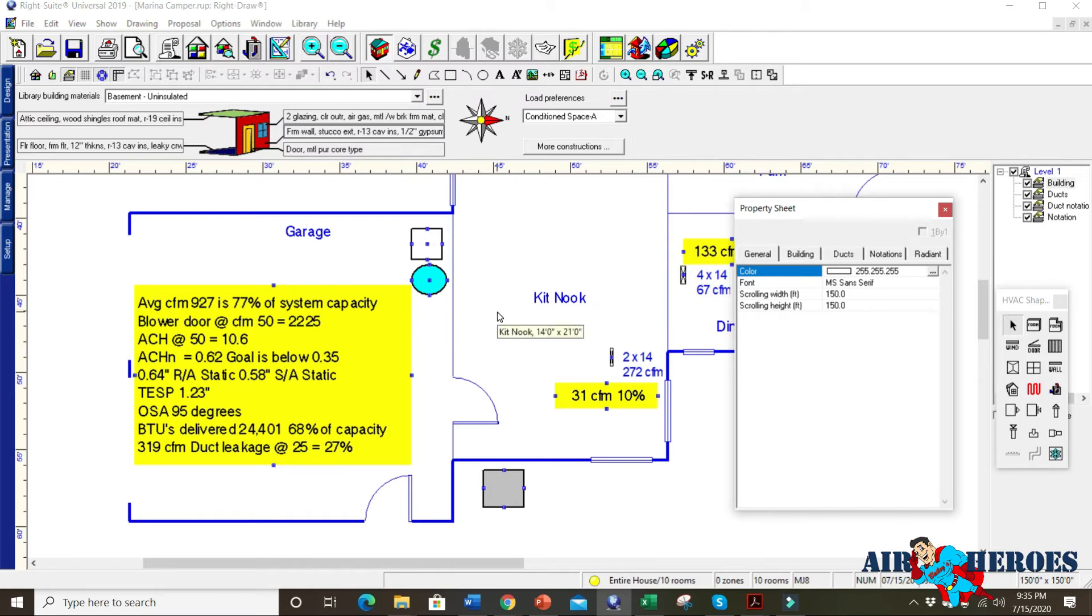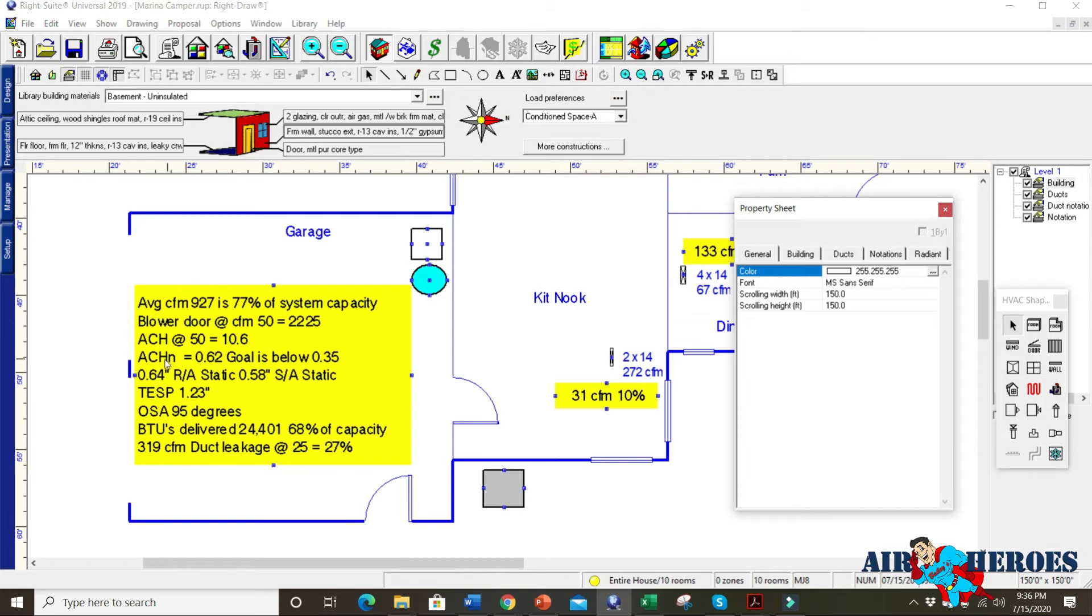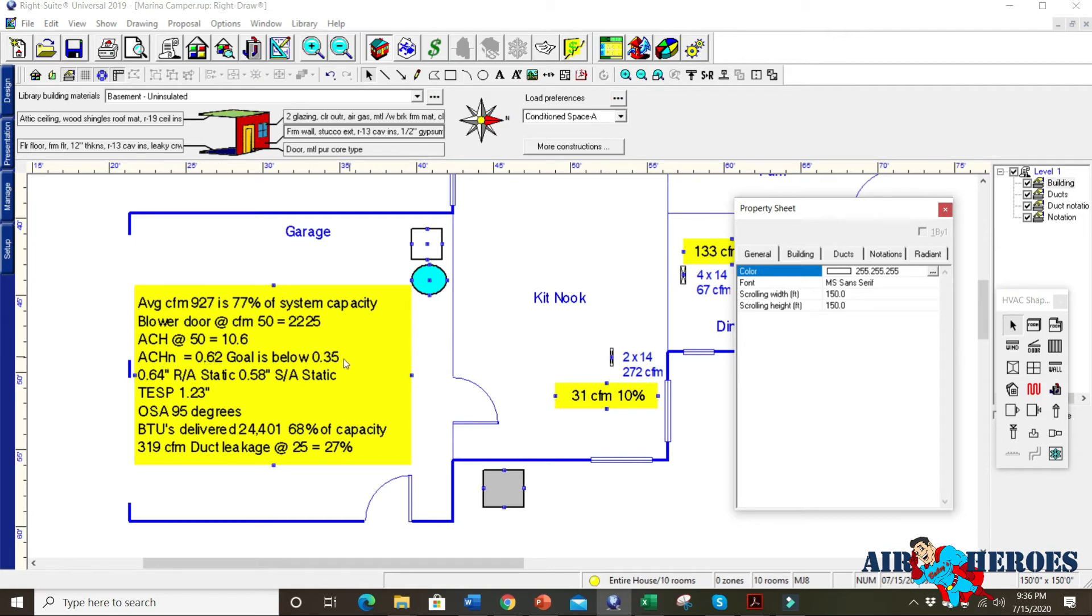And so there might be some assistance they can get through comfort home through PG&E, which is a program that gives some rebates if they do things like fix the duct work, add attic insulation, do some infiltration sealing. Because we really need to get this down to half of that because the air changes per hour at 50 Pascals was 10.6. That means they changed the air in that house 10 times an hour for the volume. Whereas air changes per natural is 0.62. We actually are looking for 0.35. If we can get it below 0.35, then we're hitting our numbers that we want to do.